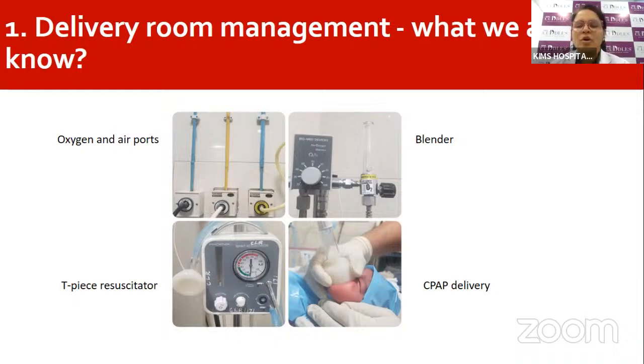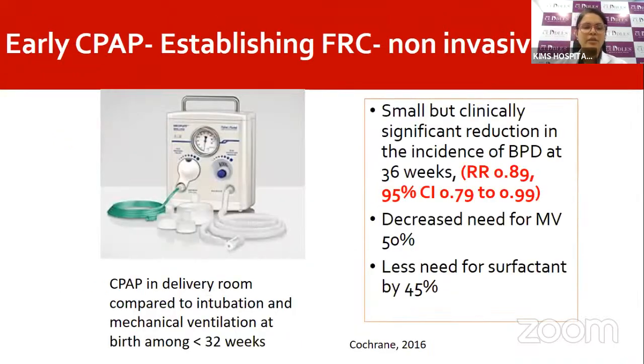And using blended air oxygen concentration has definitely been found to improve the compliance to saturations remaining within the target range, avoiding both hyperoxia and hypoxia. Now, coming to the resuscitation devices or the PPV devices, positive pressure ventilation devices, a T-piece resuscitator is found to be associated with some advantages, including the controlled and sustained delivery of peak inflation pressures, the ability to deliver PEEP or positive end expiratory pressure, lesser operator fatigue, and its feasibility as a transport device that can be used for brief provision of ventilation or CPAP while the baby is being transported. However, this critically requires an ongoing gas source, unlike a self-inflating bag, which may work without even a gas source. The T-piece can be used for providing both positive pressure ventilation as well as delivery room CPAP.